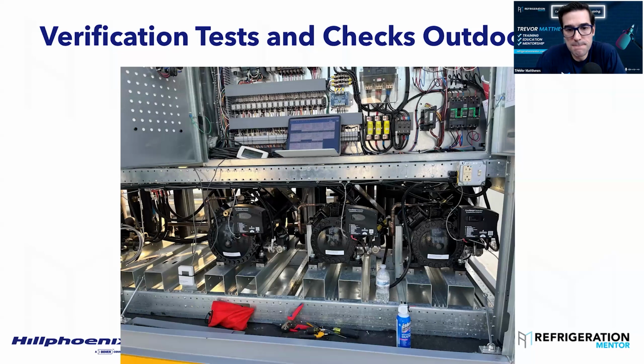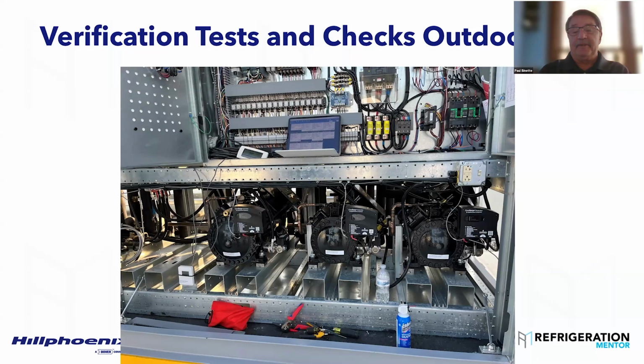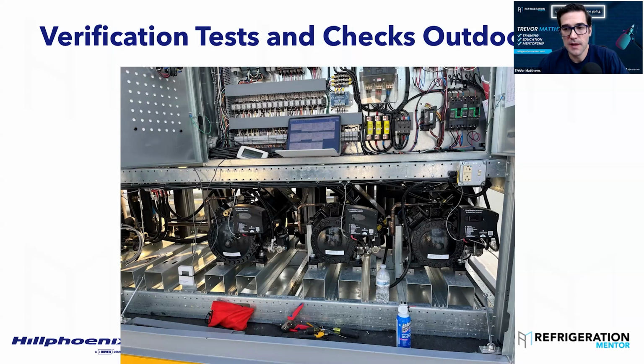Okay. I know it doesn't seem like much, but the difference between 99.9 and the next two nines is the purity, the moisture, and the non-condensables. Yeah. So if you do use a lesser grade, you're going to have to take steps to make sure you have no moisture going in, make sure you're charging with filters, do a non-condensable test after you get the rack starting.